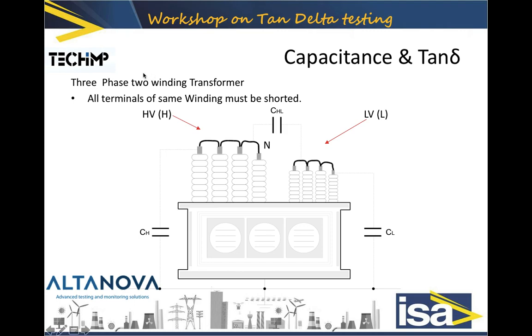For a three-phase two-winding transformer, we effectively need to measure three capacitances: CH — the capacitance between the high voltage winding and ground; CL — the capacitance between the low voltage winding and ground; and CHL — the capacitance between the high voltage winding and the low voltage winding.